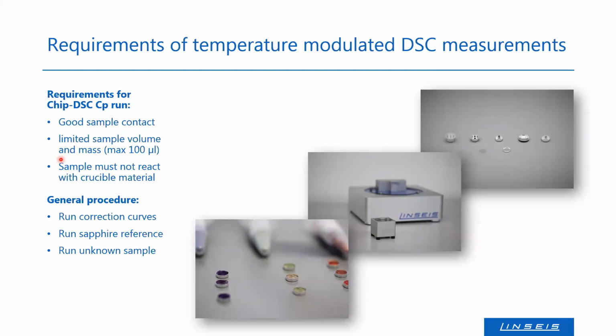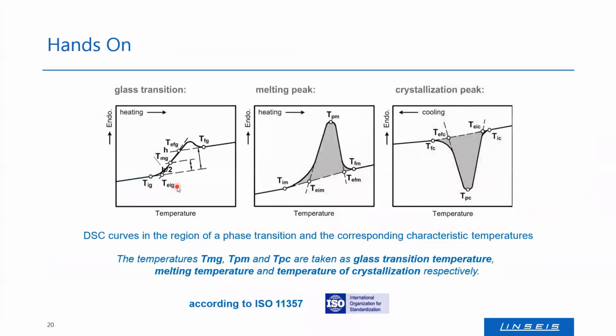And there are basically 3 steps we are performing. At first, we have to run the correction curve. We have to run, for example, a sapphire reference, but of course, it's also possible to use other materials as a calibration. You just have to make sure you have enough literature values. There are some in our software. And of course, the material should be inert within the temperature range you're interested in. And then the third step is you can run your unknown sample. I already told you we want to do a short hands-on. So let's go to the software maybe.